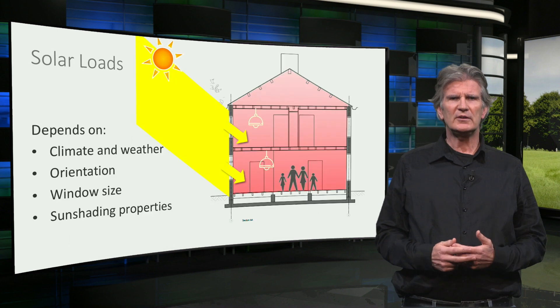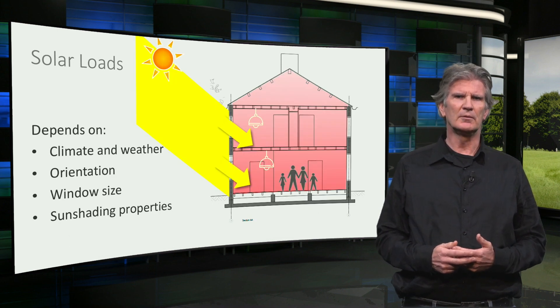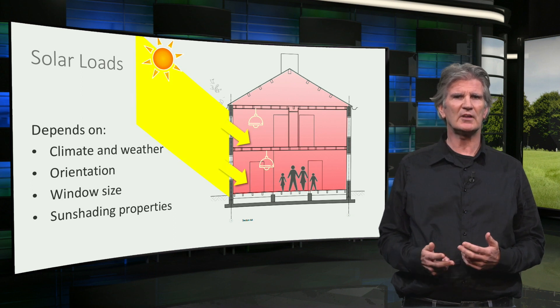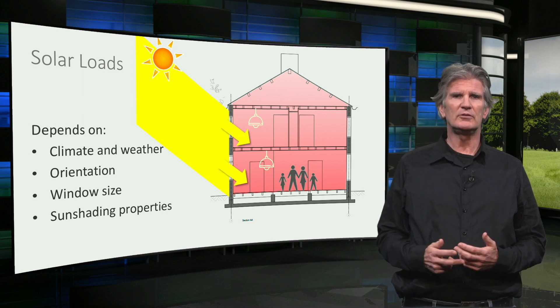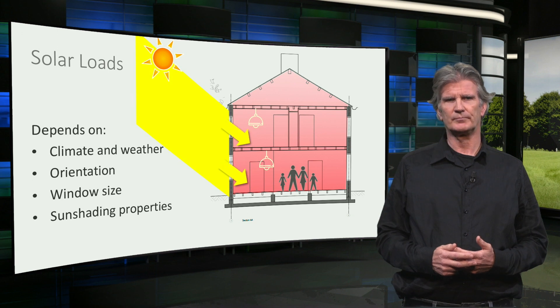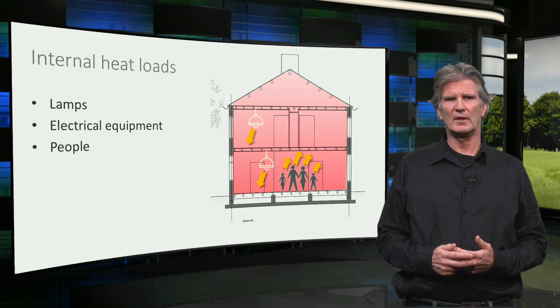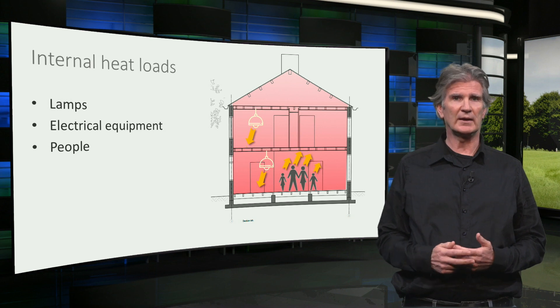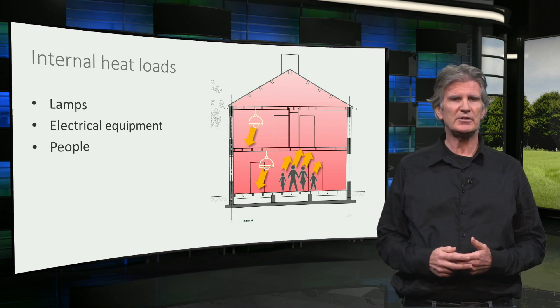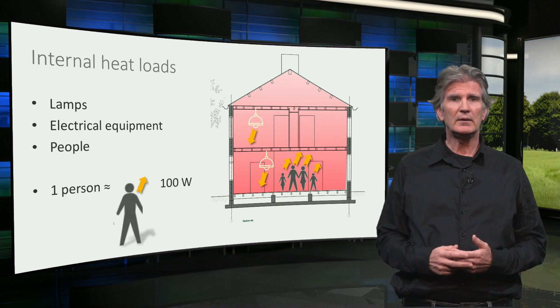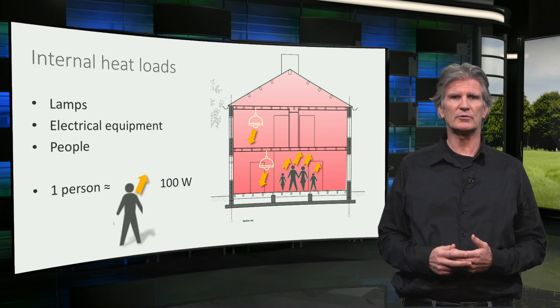When the sun is shining, there is an incoming heat flow through the windows. The amount of incoming energy depends on the orientation and size of the windows and the sun shading properties of the windows. Inside the house there are also heat sources like the heat produced by lamps, electrical equipment, and even the people themselves. Remember, one person produces on average 100 watts of heat.